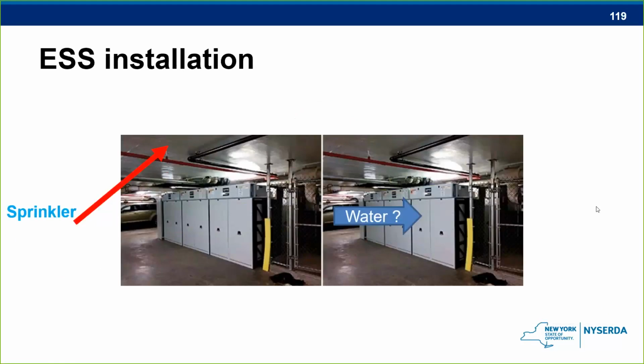Just a couple of pictures of some installations here. I usually ask the class, take a look. This is an energy storage system in a garage in downtown Manhattan. What chemistry is that? Most people have no idea. That's actually a lead acid based chemistry. You wouldn't be able to tell unless we had signage that said this chemistry is lead acid based. So making sure that the proper signage is there is important.